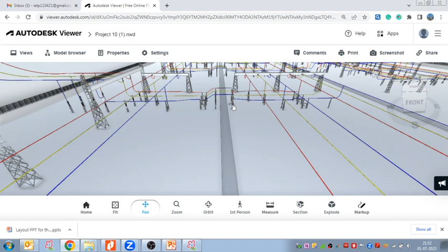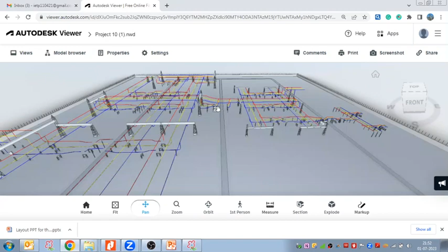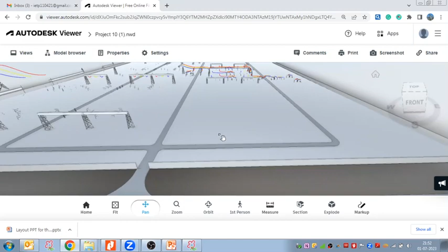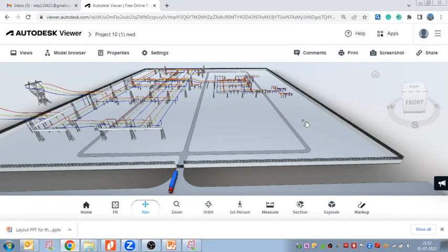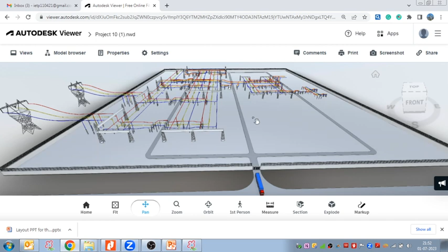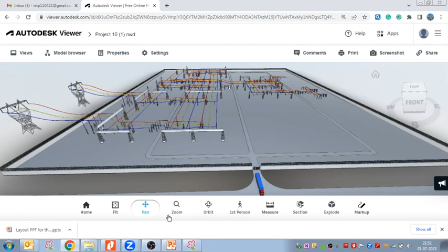So this internal road is 3.75 meter, and the main road coming to the transformer is 5.5 meter. If the control room building is located nearby, we can take around 4 meter, or the same 5.5 meter, if there is any possibility that the transport vehicle carrying the transformer needs to pass that road. In that case we take 5.5 meter; if not, we take 4 meter road for the control room building.